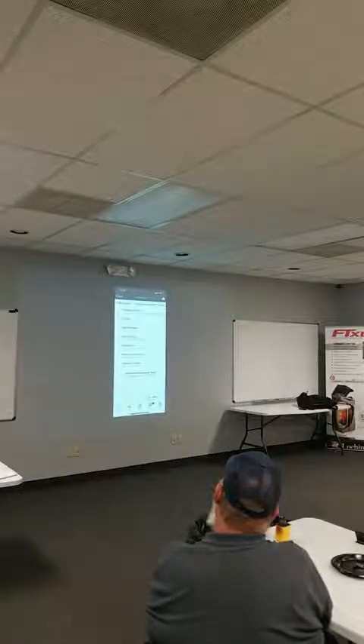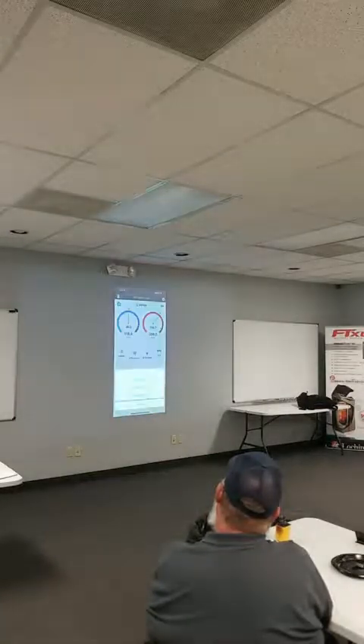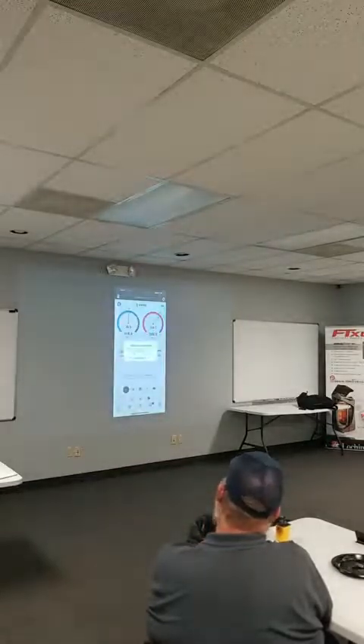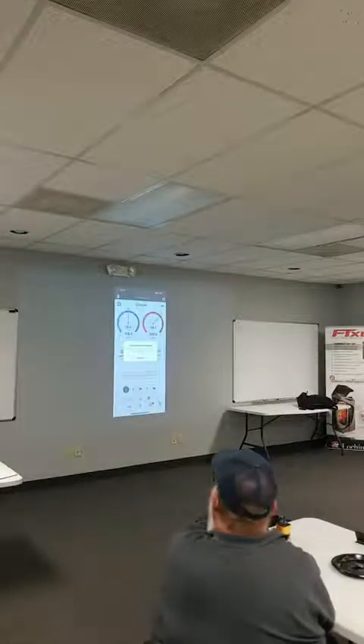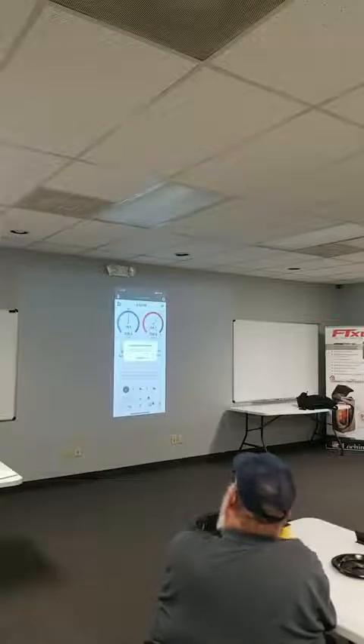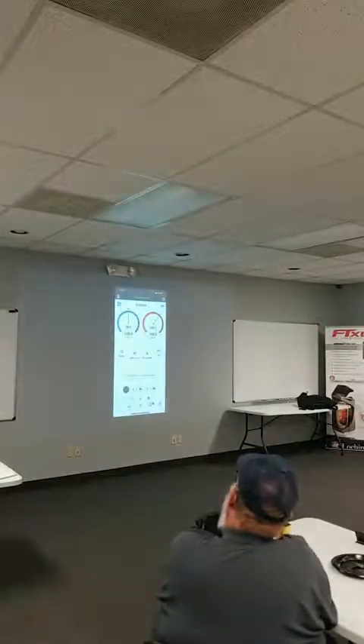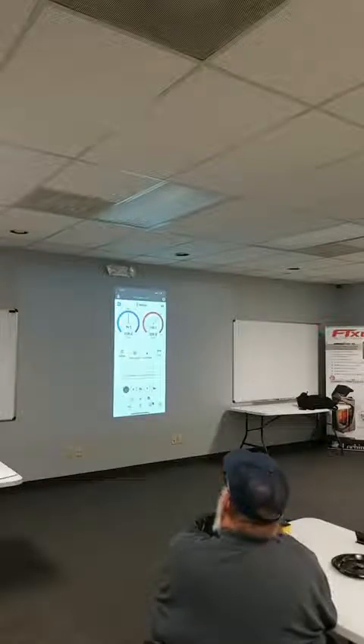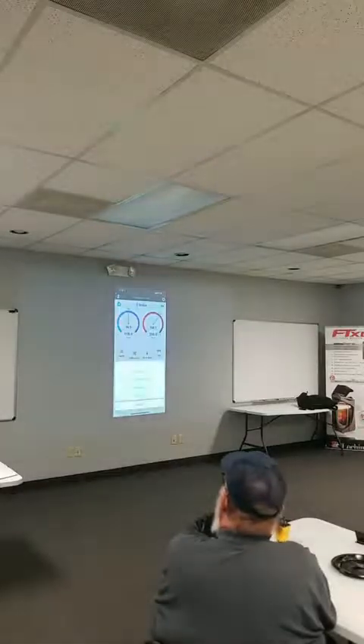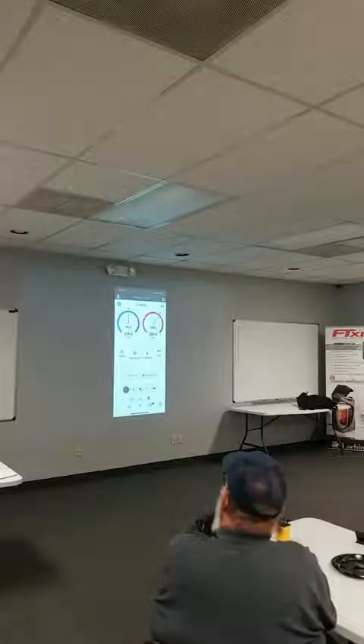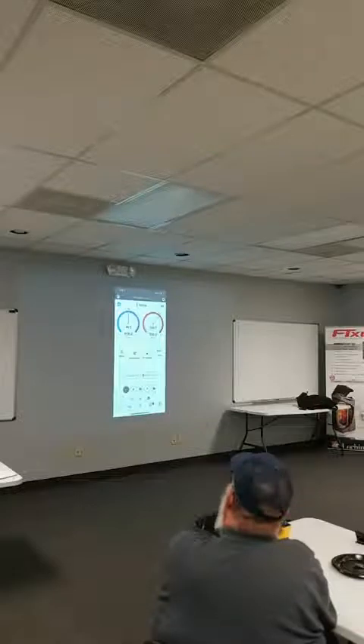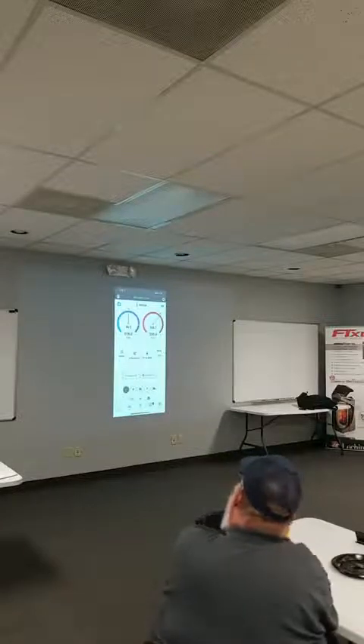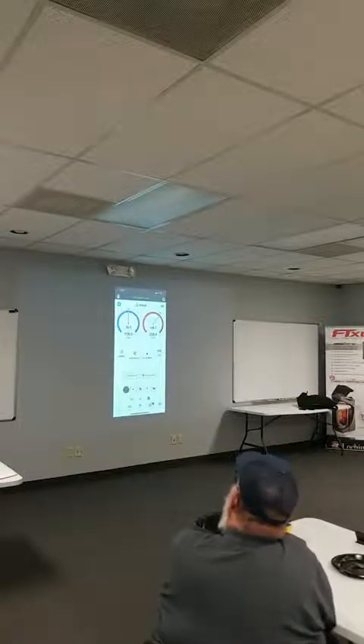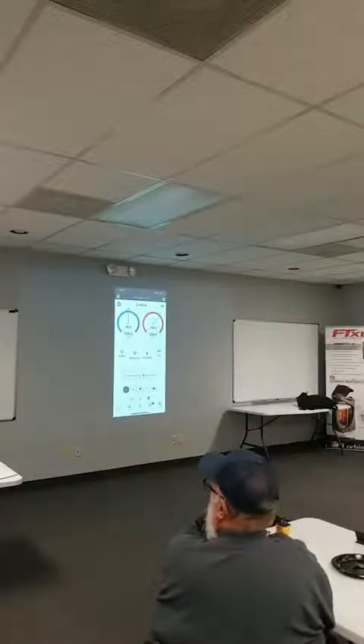So when you go home here and you set the benchmark, notice those targets will tighten right up, okay? Now what it did is it took that huge target zone that we had and narrowed it down, saying, okay, now this is the range that it should run in. If I open that back up again, I can just hit the plus key down here and clear the benchmark, and the target will back up, right? So the idea here is any suction pressure in that range is okay, but once you get it dialed in, it's going to dial it into a more definitive target.